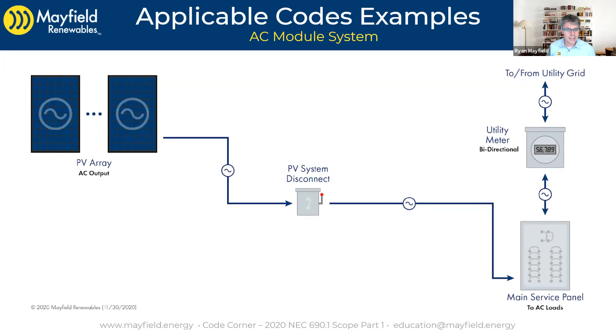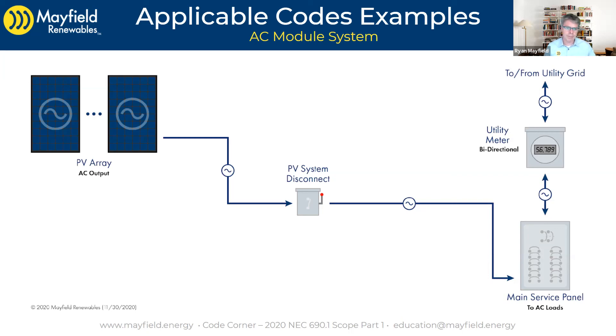The other one that's easy to consider here is an AC module system. These are becoming actually quite popular — a few years ago we weren't seeing very many, now we're seeing more and more. AC modules are different than a PV module with a micro inverter attached; it's a listed assembly, so it's different. But in a sense it's still an interactive system — all we're doing is taking the inverters and putting them up at the module level, so each unit has an AC output. There's a definition you can go look at, but that is an AC module. When it comes to applying the code and that system disconnect, it's the same as what we were looking at for a separate inverter system.